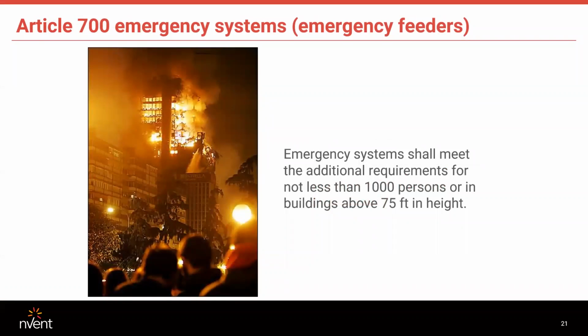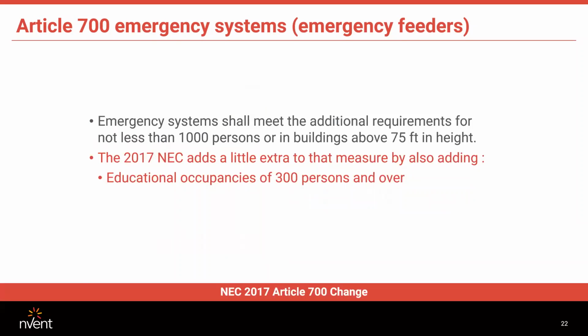And Article 700 requires emergency systems to meet these requirements. So basically, when you have a building that houses 1,000 people or more, or is above 75 feet in height, you're going to need to have those feeders fire rated for 2 hours. Again, if you have a high-rise building, or a building that exceeds an occupancy of 1,000 people, you will need to have fire-rated emergency feeders in that building.